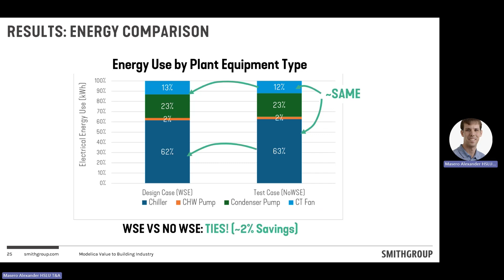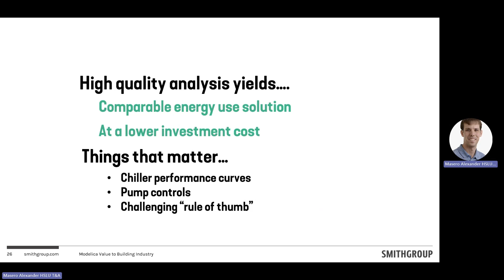Some things that matter from this: chiller performance curves, pump controls, challenging rules of thumb. We're able to test, hey, let's just run the condenser water pumps and drive the lift down. Will that actually increase energy use in the simulation? So that would be a first rule of thumb for mechanical engineers or plant operators.